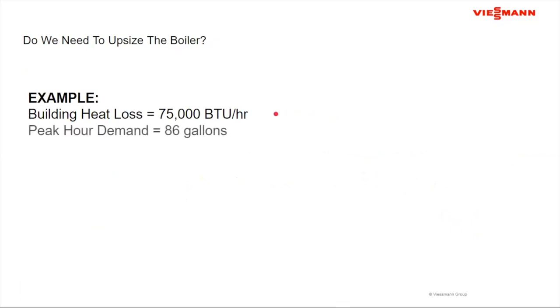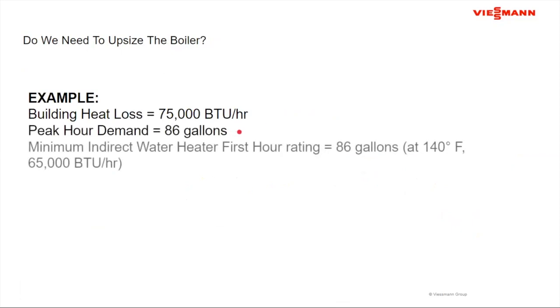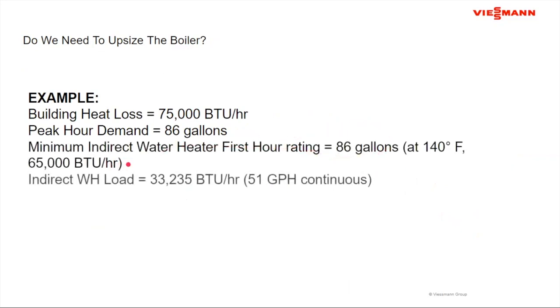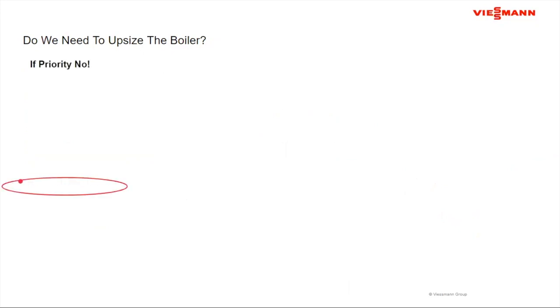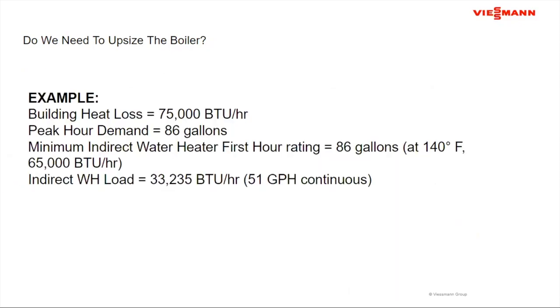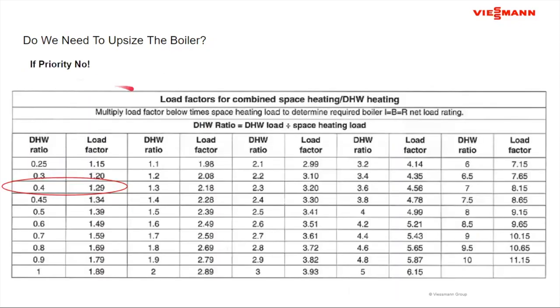If I'm going non-priority, I have a 75,000 BTU boiler. My peak demand's 86 gallons. And we did through the calculation, as I said, I don't need 65,000. I actually need 33,000. So immediately somebody says, okay, let's add 75 and 33, and that's the size of my boiler. Okay. But if I'm trying to reduce the size, there is the option of applying a load factor to be able to right size the application.